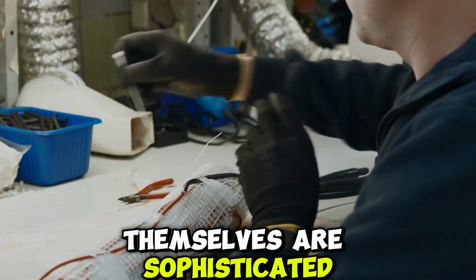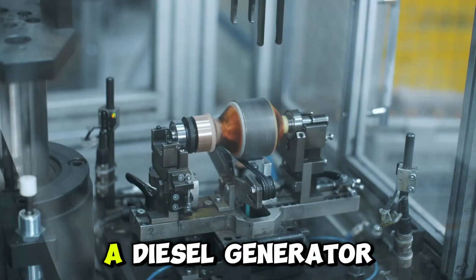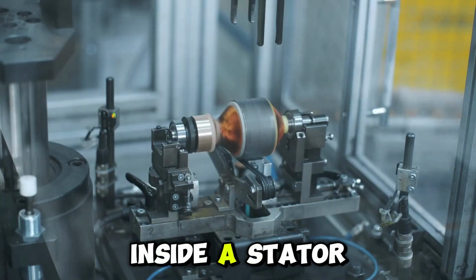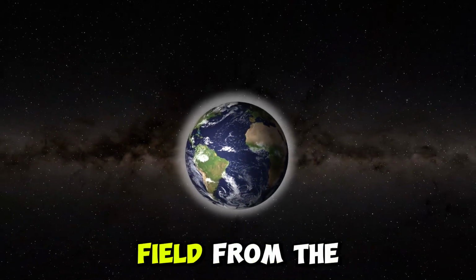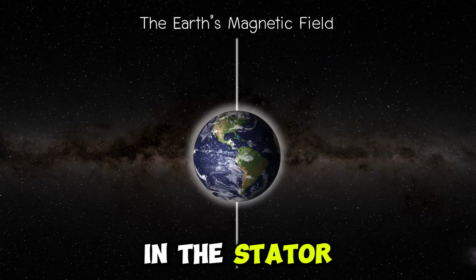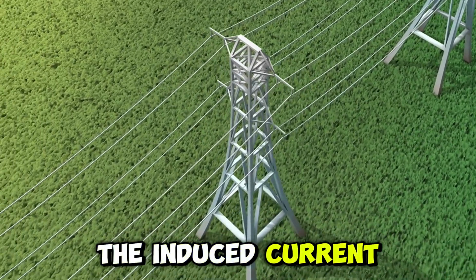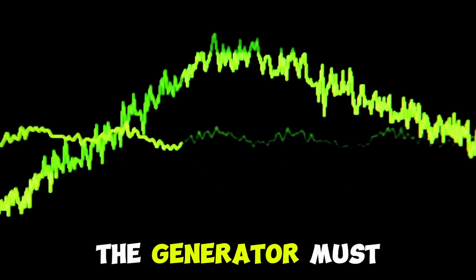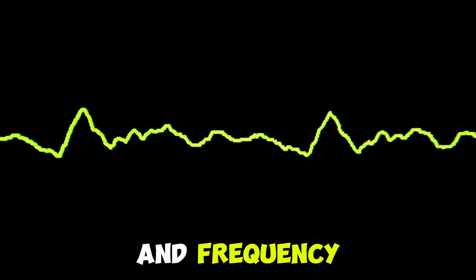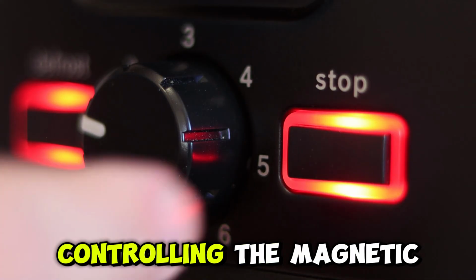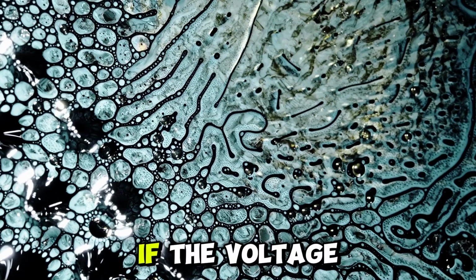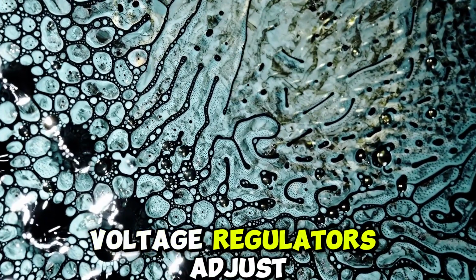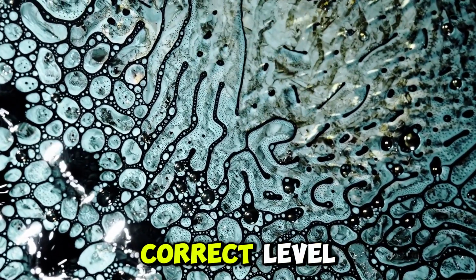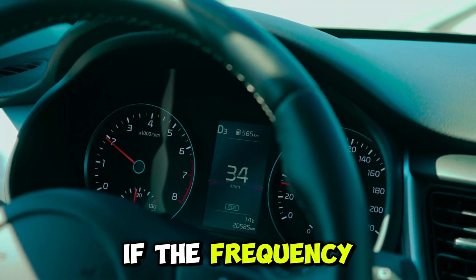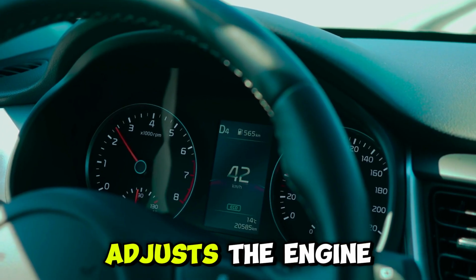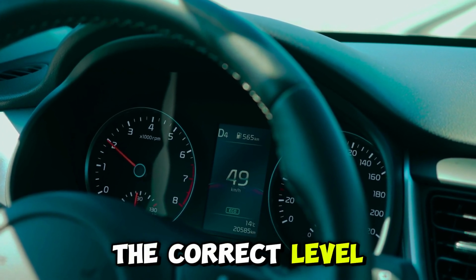The generators themselves are sophisticated electrical machines. A diesel generator contains a rotor that spins inside a stator. The rotating magnetic field from the rotor induces electrical current in the stator windings. The induced current is the electrical output. The generator must produce the correct voltage and frequency. The voltage is regulated by controlling the magnetic field strength. If the voltage becomes too high or too low, voltage regulators adjust the magnetic field to bring the voltage back to the correct level. If the frequency becomes too high or too low, the engine governor adjusts the engine speed to bring the frequency back to the correct level.